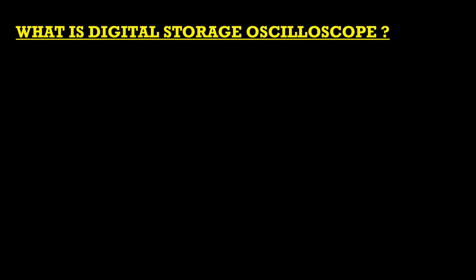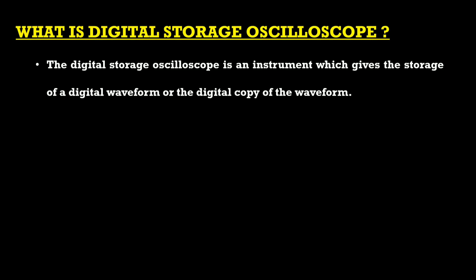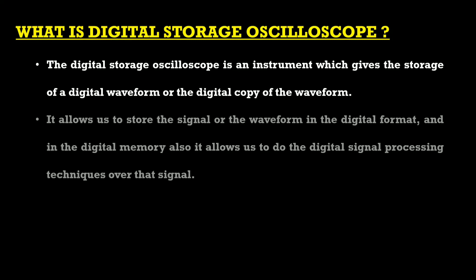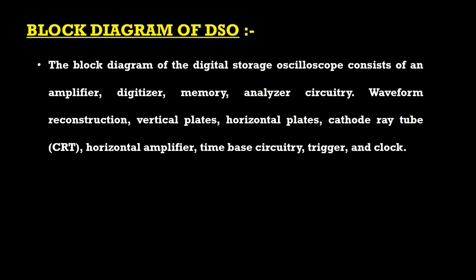Now let us define the Digital Storage Oscilloscope. The DSO is an instrument which provides storage of a digital waveform, or a digital copy of the waveform. It allows us to store the signal in digital format and in digital memory. It also allows us to apply digital signal processing techniques to that signal.